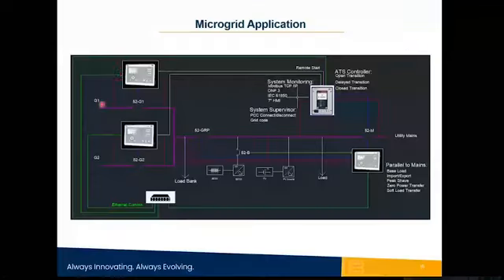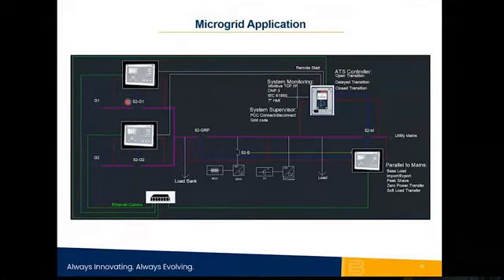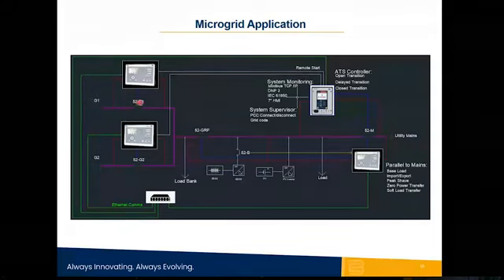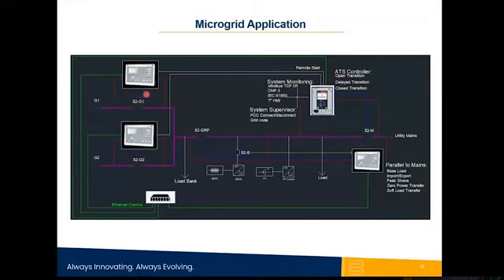So having said that, let's talk about a specific microgrid application. This is just an example with two generators in parallel. The first part of this, most people are familiar with. You have generator 1, generator 2, the breaker for generator 1, and the breaker for generator 2. Here are DGC 2020 HD number 1 and DGC 2020 HD number 2, sensing the load bus and the generators. These two 2020 HDs perform synchronization, load sharing, and so on.